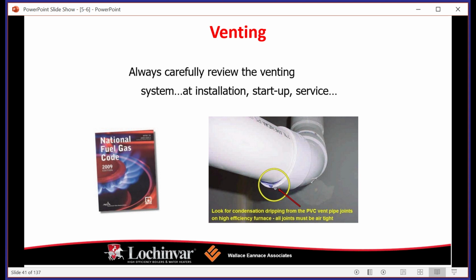Again, on PVC pipe, you're never going to want to see anything leaking. You're going to want to prime those joints. You're going to want to glue them together. If your installers are not experienced with larger size PVC fittings, they need to make sure to seat them correctly and then keep them seated until your sealant is adhered properly. Because if you've ever done that with, say, 4-inch flue pipe, and you stick it in and seat it to the bottom of that fitting, it'll push itself out.